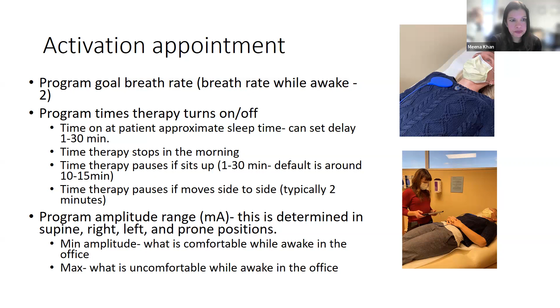Are they capturing most of the time? What milliamp is that? How is the patient tolerating it? And then you'll make adjustments in the range based on that. So during the 6 weeks between the visits, the device is analyzing the breath every minute, and it increases the milliamplitude until that programmed breath rate is met. And that's what we call capture.